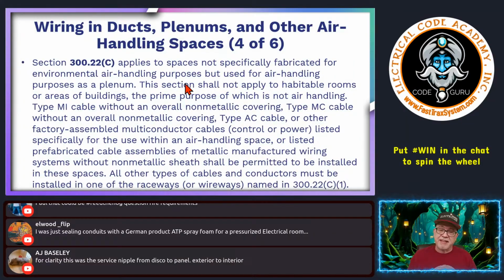Now, so if that's the case, 300.22(C) applies to spaces not specifically fabricated. They're just being used for environmental air handling purposes, like a plenum. Remember, sucking air from the room up into this open cavity. So think of it as one big plenum space, and then into the unit, which is totally different than being individually ducted, right? So this section shall not apply to habitable rooms or areas of buildings like where we're down here. It won't apply to that because it's just sucking the air normal, okay? The prime purpose of which is not air handling.